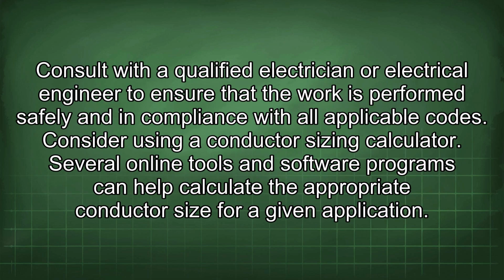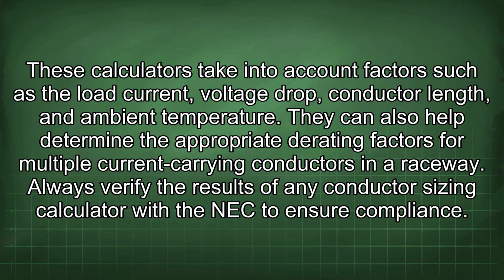Consult with a qualified electrician or electrical engineer to ensure that the work is performed safely and in compliance with all applicable codes. Consider using a conductor sizing calculator. Several online tools and software programs can help calculate the appropriate conductor size for a given application. These calculators take into account factors such as the load current, voltage drop, conductor length, and ambient temperature. They can also help determine the appropriate derating factors for multiple current-carrying conductors in a raceway. Always verify the results of any conductor sizing calculator with the NEC to ensure compliance.